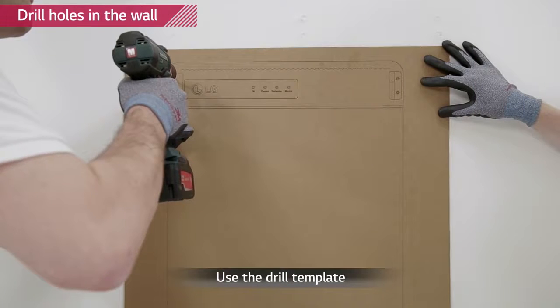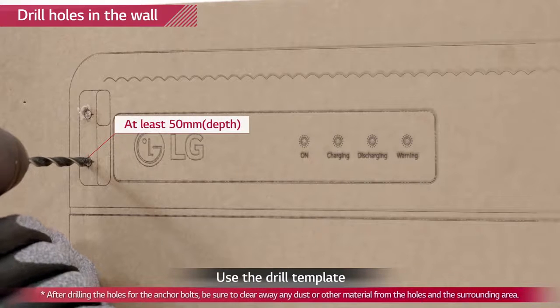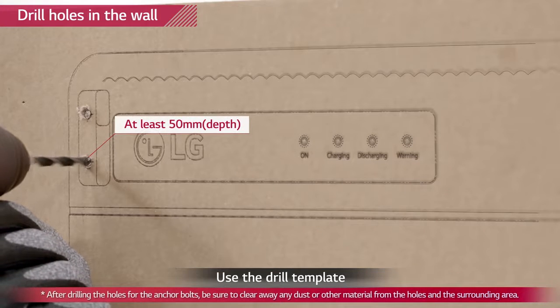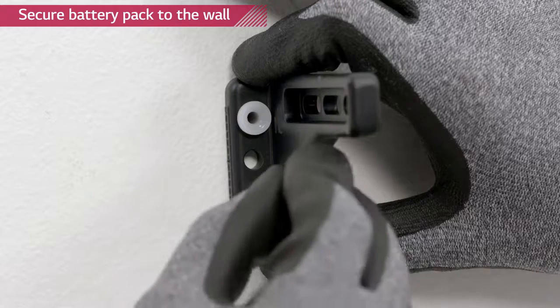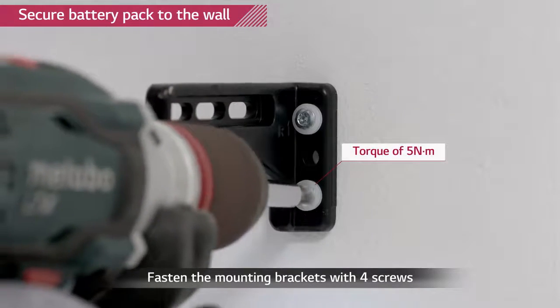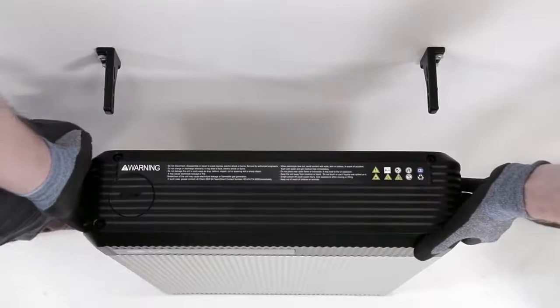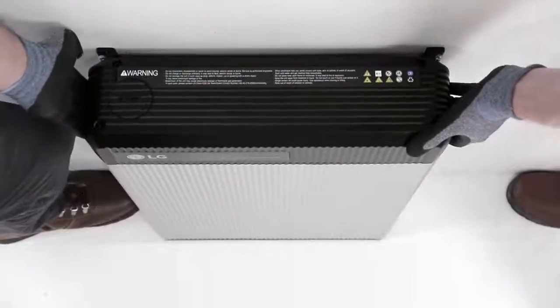Drill four holes into the wall for M6 screw anchors using the drill template. The depth of the hole should be at least 50 mm each. Fix the provided mounting brackets to the wall with M6 screw anchors with a torque of 5 Nm. Remember that the battery pack needs to have a distance of at least 9 mm away from the wall. Place the RESU battery pack between the wall mounting brackets.